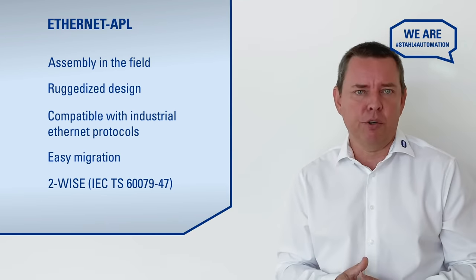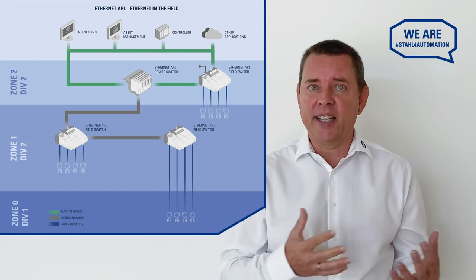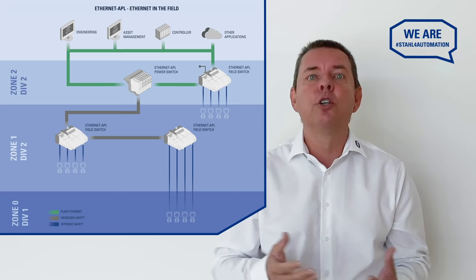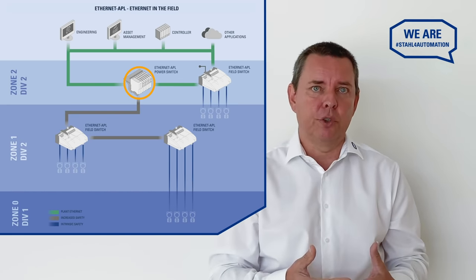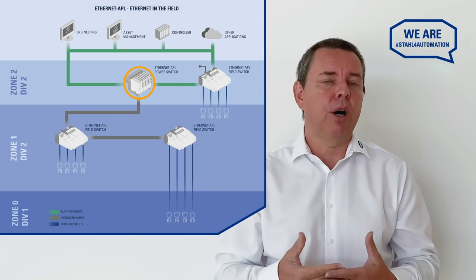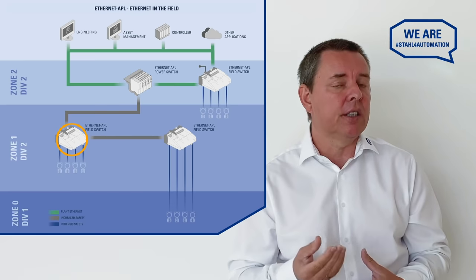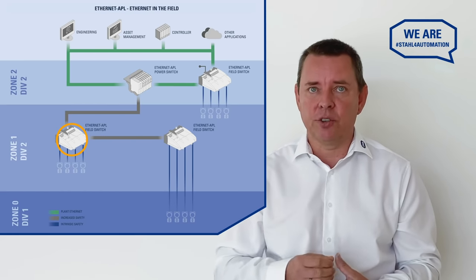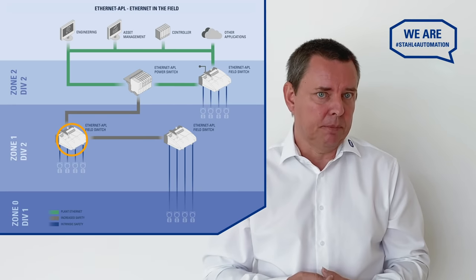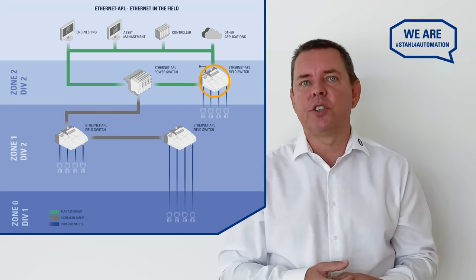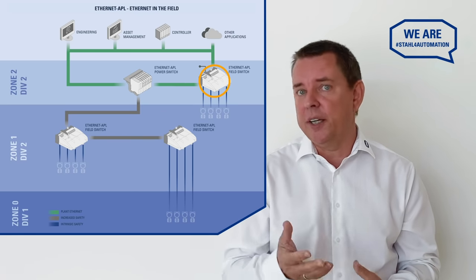What makes Ethernet APL so powerful is its support for various topologies, from the classical trunk and spur known from fieldbus, to star topologies. The Ethernet APL power switch converts four-wire networks to two wires and can power up to approximately 50 field devices, including Ethernet APL field switches in the hazardous area, which connect the field devices to the network by intrinsic safety. Ethernet APL field switches can also be installed in a standard four-wire Ethernet network, say in your control room.